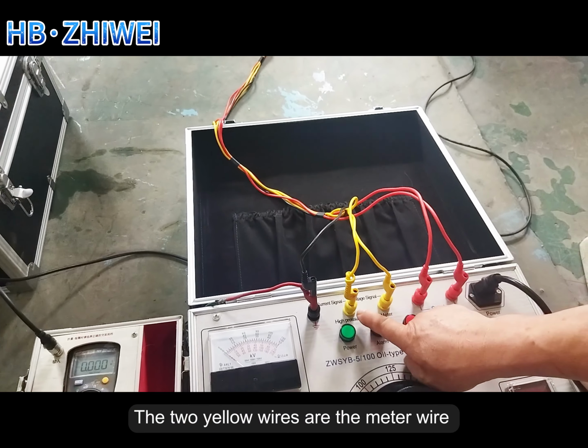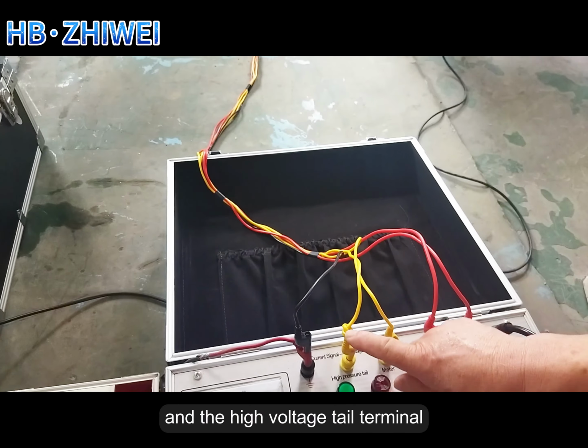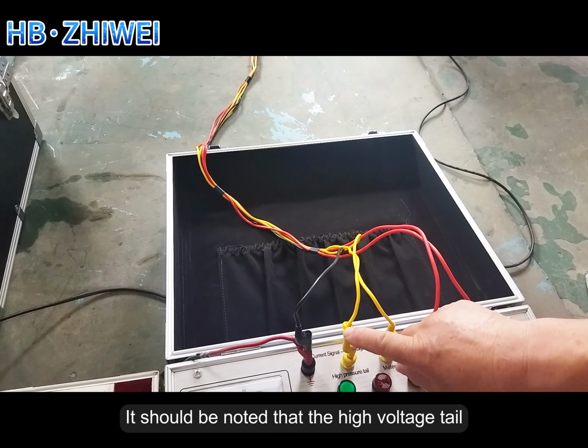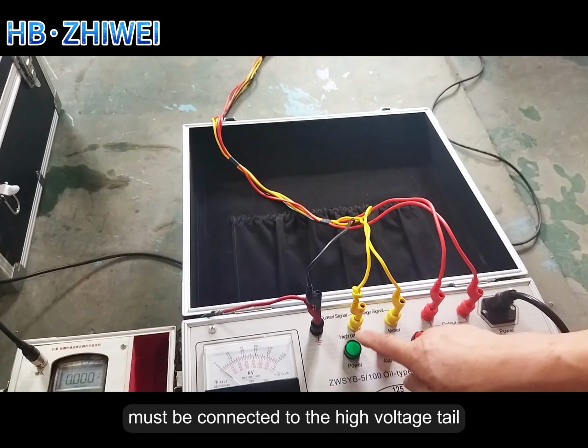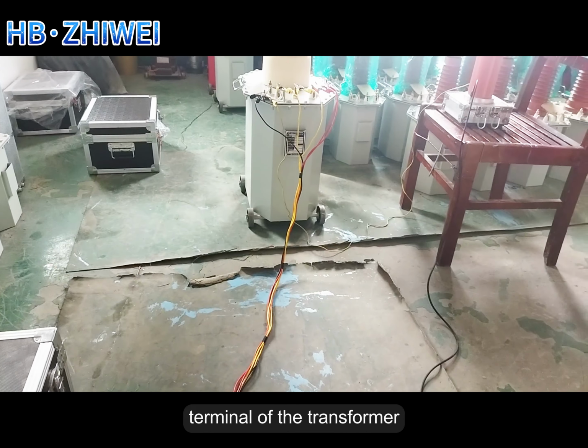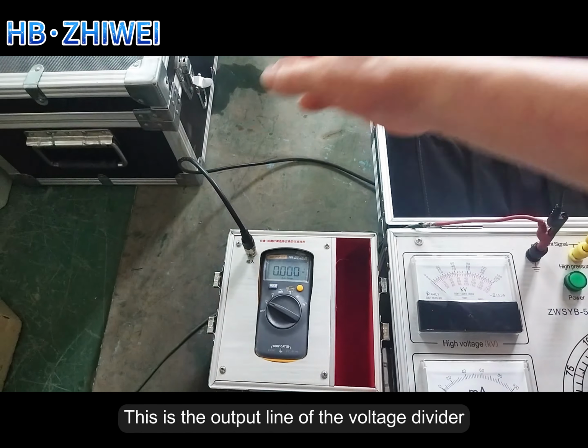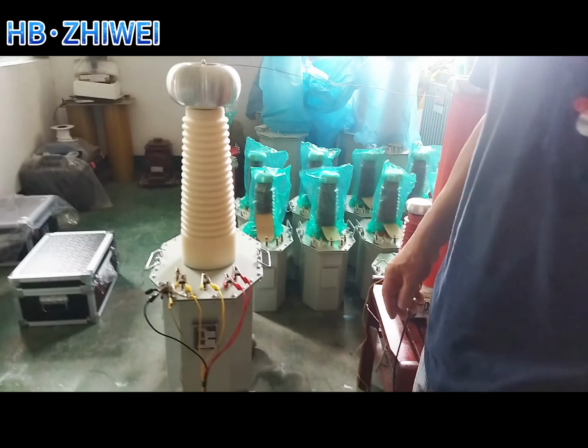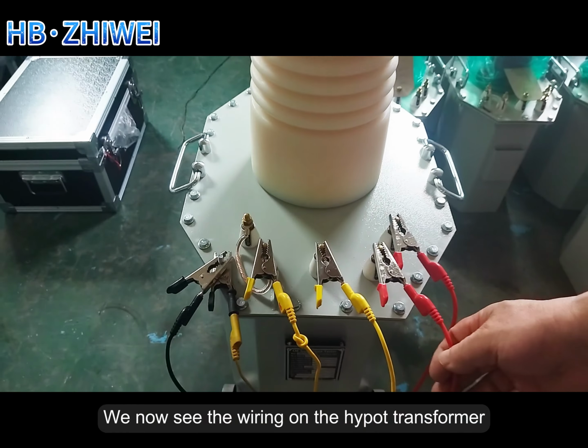The two yellow wires are the meter wire and the high voltage tail terminal. It should be noted that the high voltage tail must be connected to the high voltage tail terminal of the transformer. This is the output line of the voltage divider, which is used to record the voltage value of the test. We now see the wiring on the Hipot transformer.